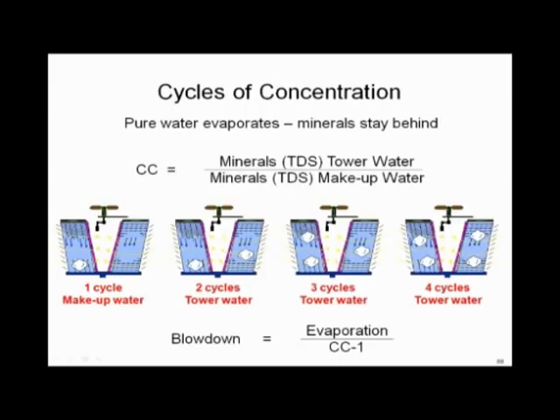Let's look quickly at cycles of concentration because it's in the code. A lot of engineers and people who have never really dealt with this have heard about cycles of concentration at the cooling tower. As I evaporate water off in a tower, what I call the rocks stay behind, so sooner or later I've got to have some blowdown water going down the drain, or my tower's going to cake up as one great big rock. This is determined by the cycles of concentration.